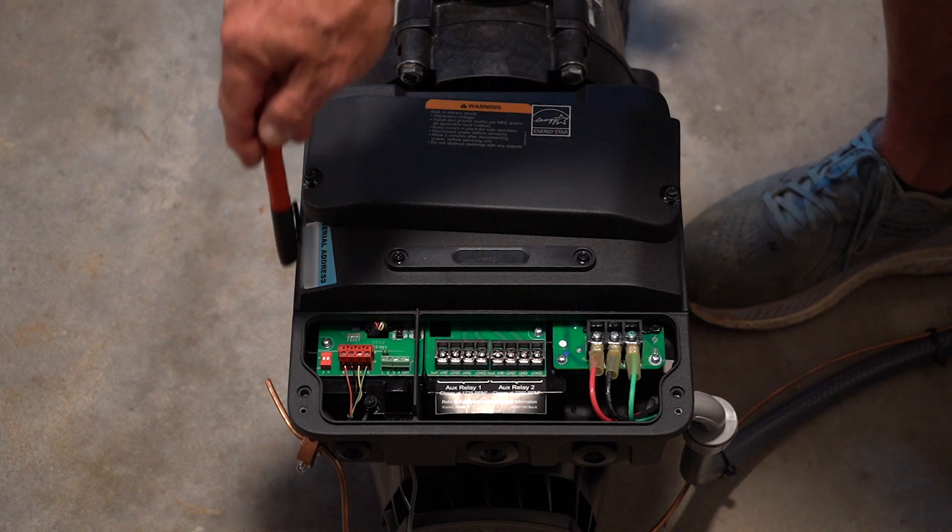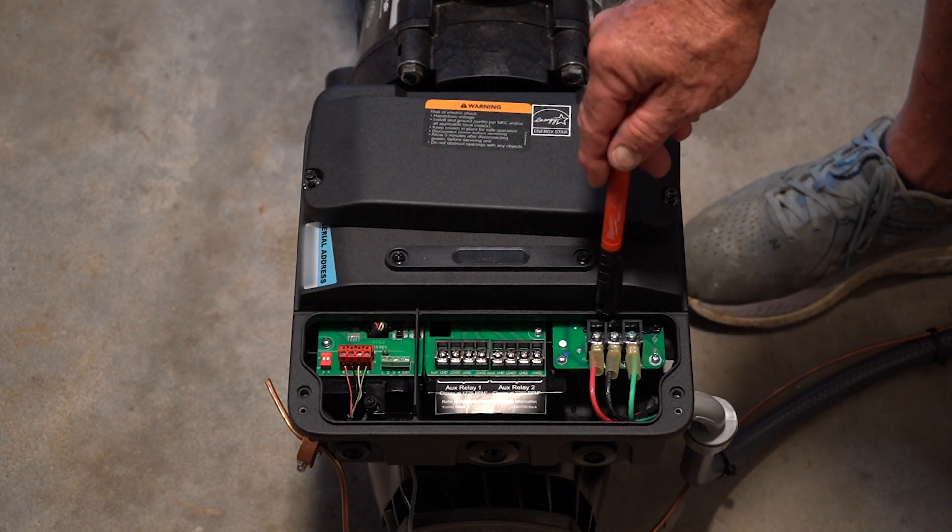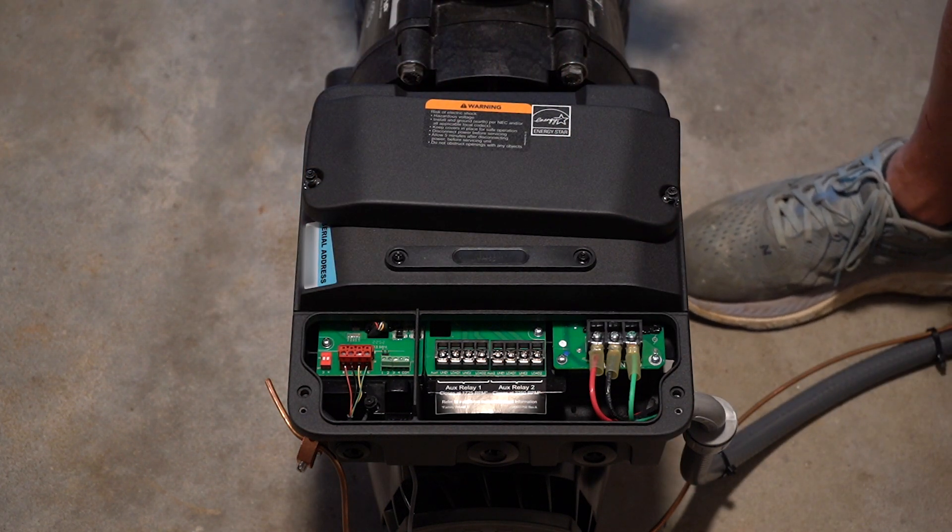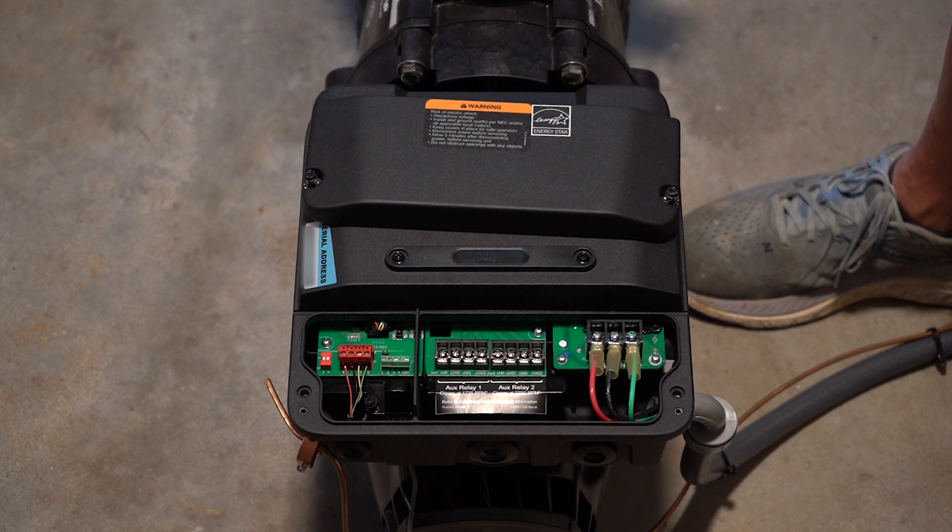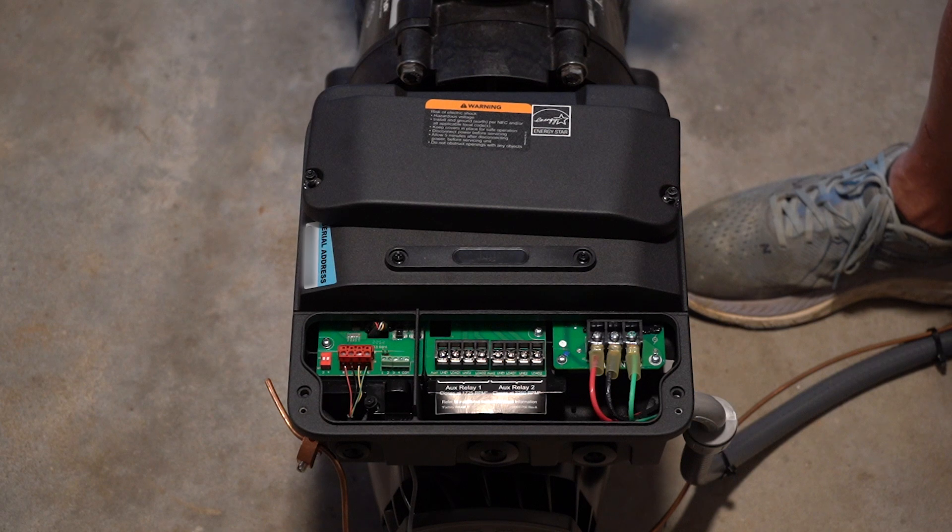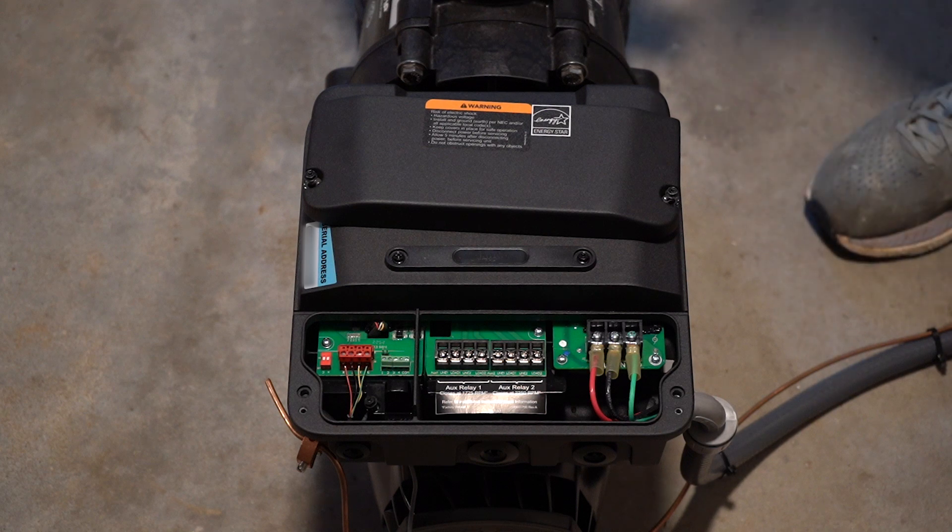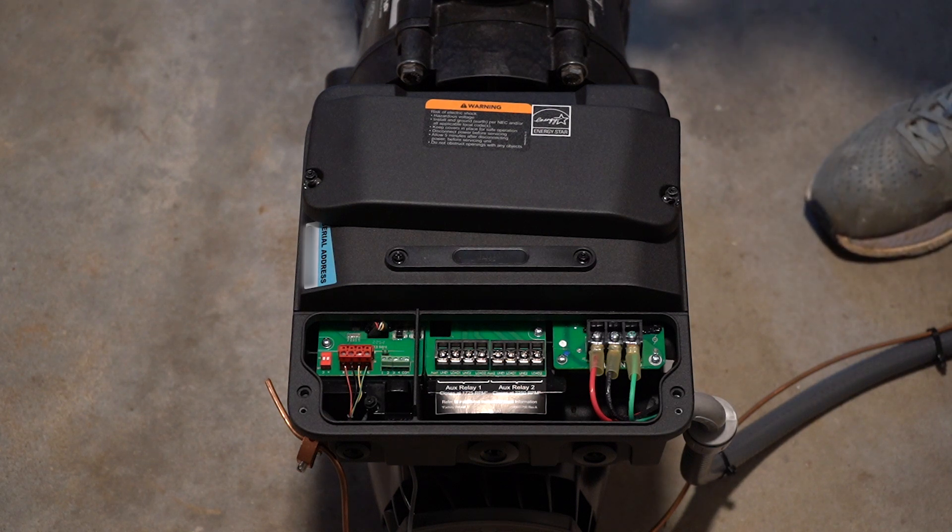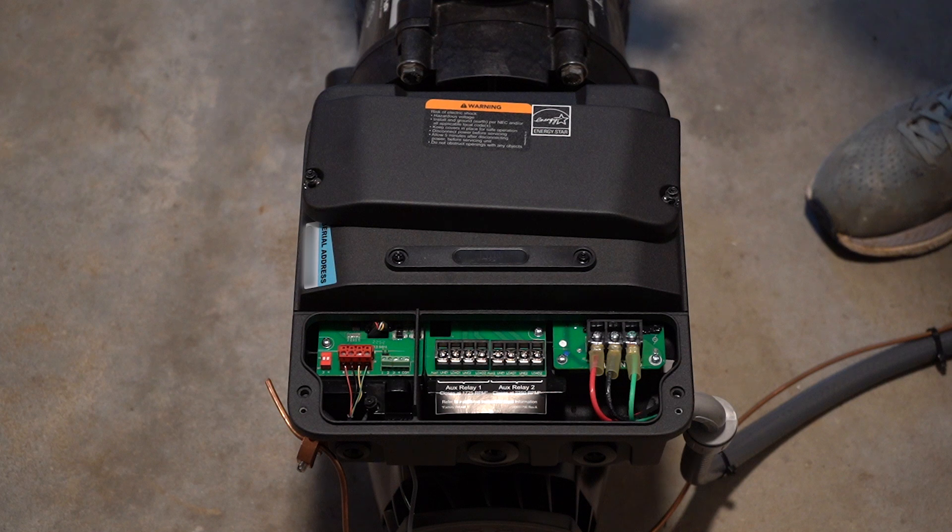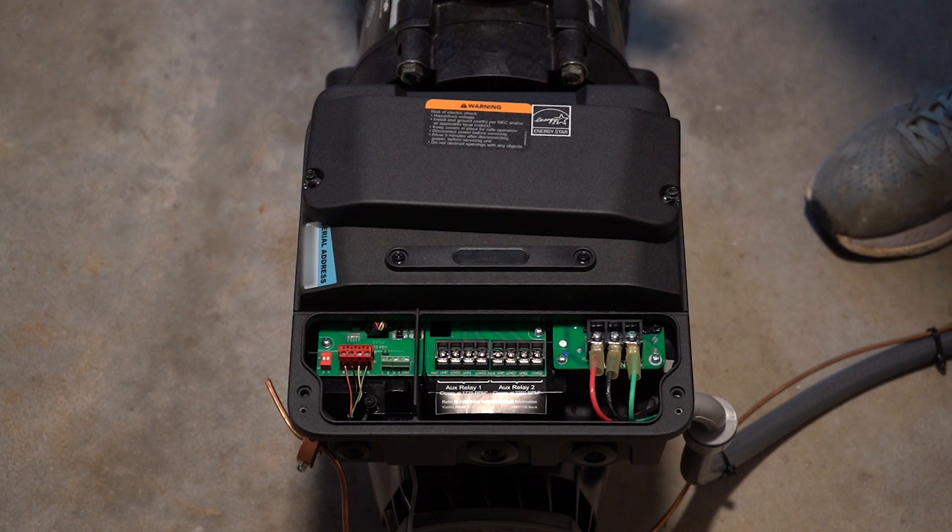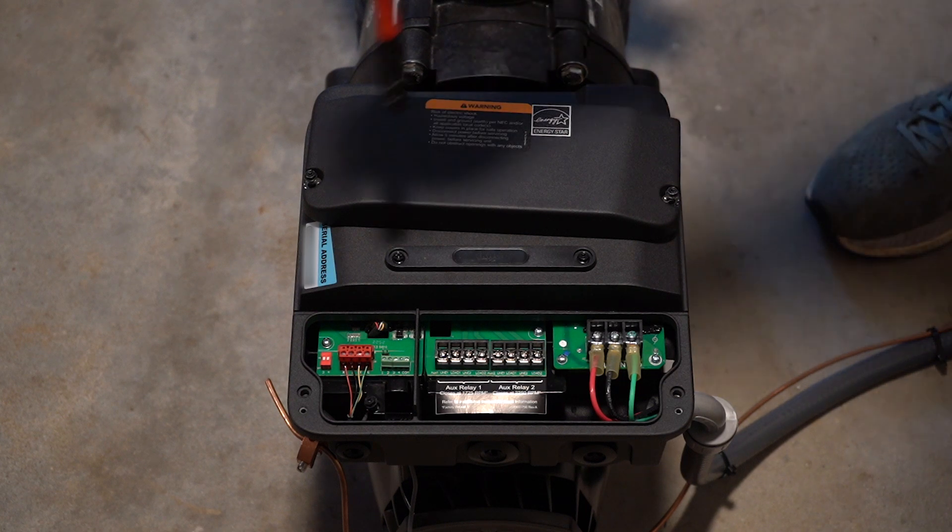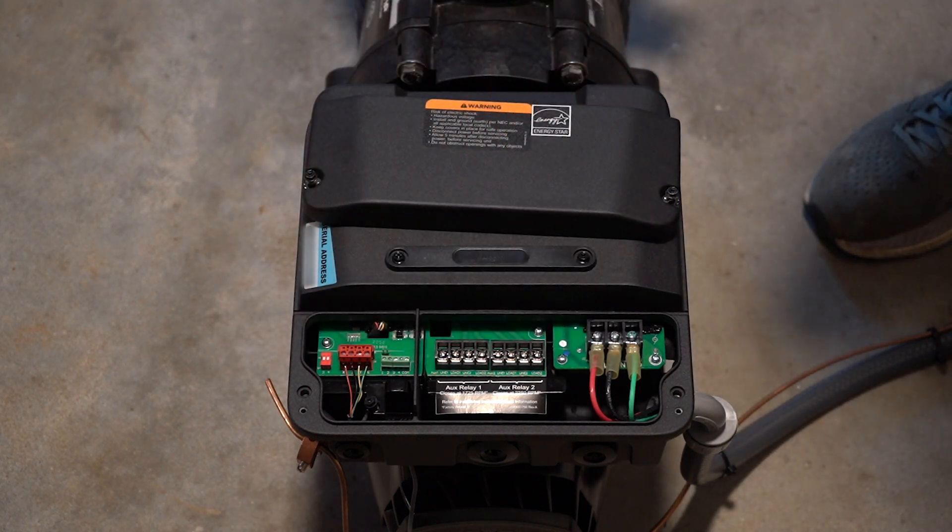Of course, make sure that it's bonded correctly, make sure that you're through a GFI circuit breaker. And particularly, this pump requires a 20 amp 240 volt. And it would have to be a Siemens circuit breaker. Siemens is the only one that actually manufactures a circuit breaker that's designed for pool systems. And you'll notice that it's a lot bigger than a regular circuit breaker. It has special circuitry in it to deal with what I'll call stray voltages that come in through your bonding or your grounding, which is very common in pool applications.